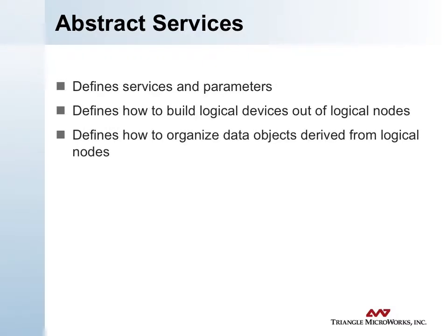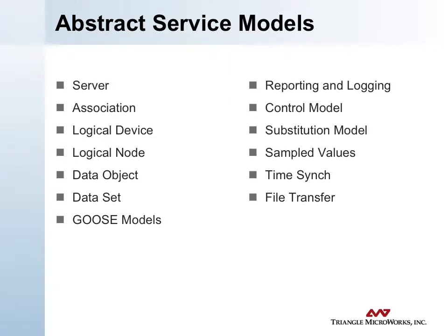Part 7.2 of the document set, the Abstract Communication Service Interface, defines the services and their parameters. It defines how to build logical devices out of logical nodes, and it defines how to organize the data objects derived from the logical nodes. Part 7.2 defines abstract models for a server, associations, and logical devices and nodes. It also covers abstract services like substitution and sampled values, which are common across a wide range of utility industry applications.